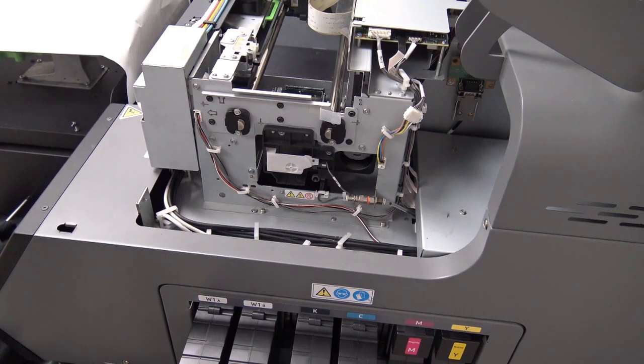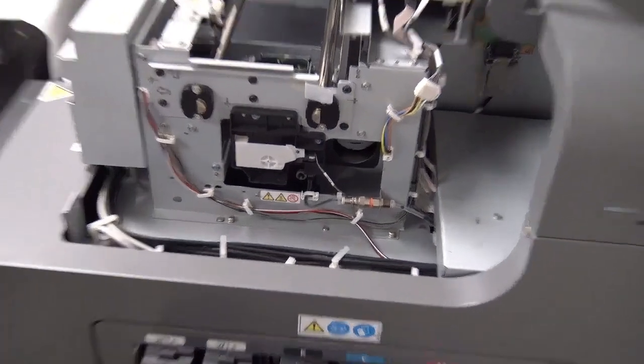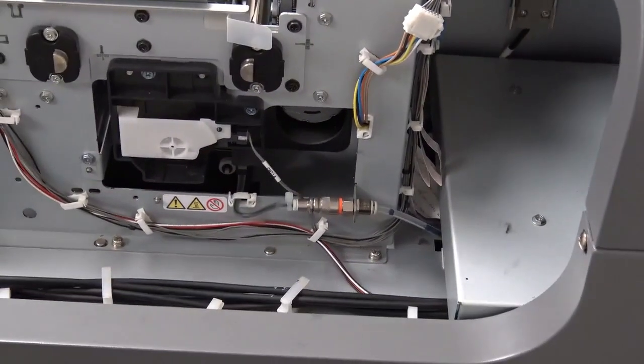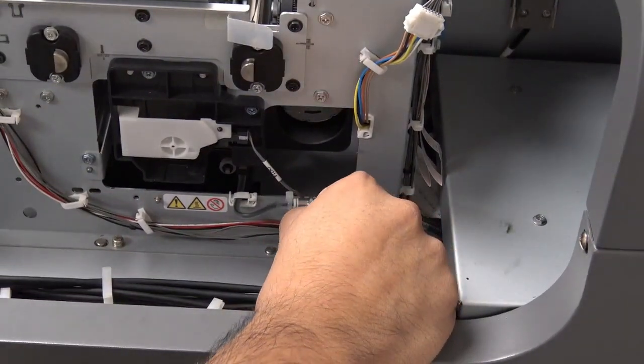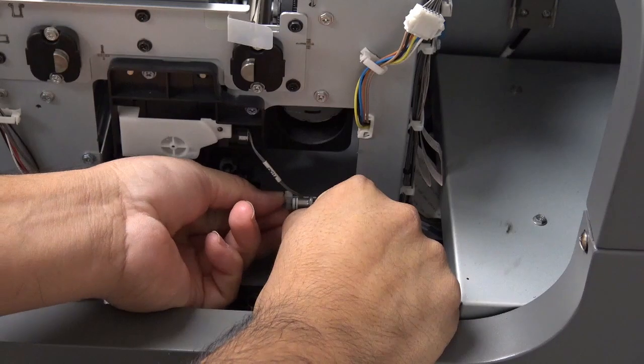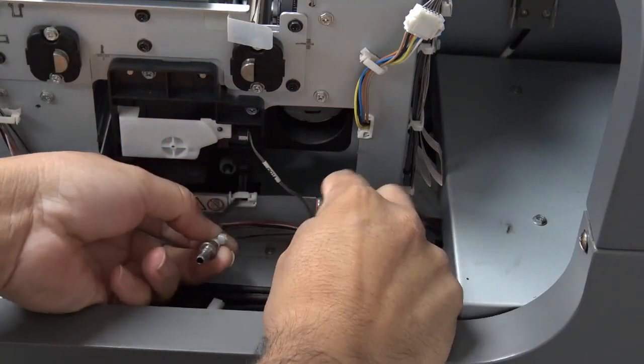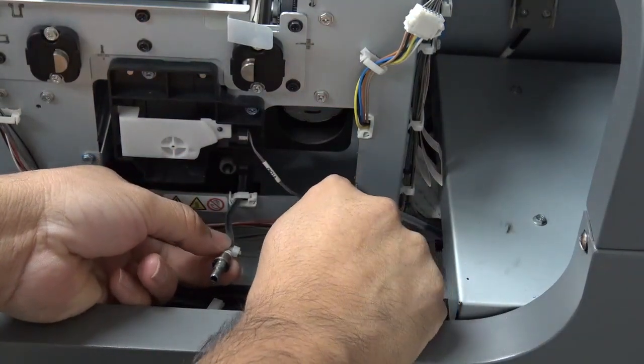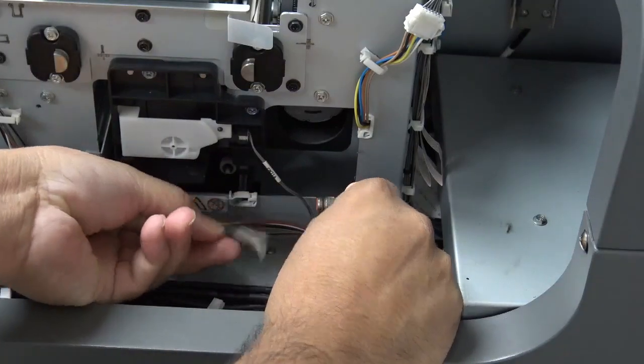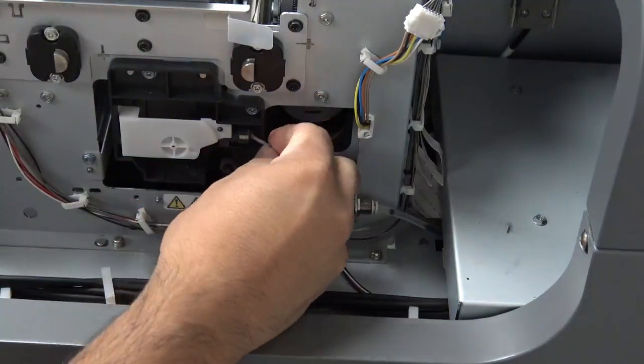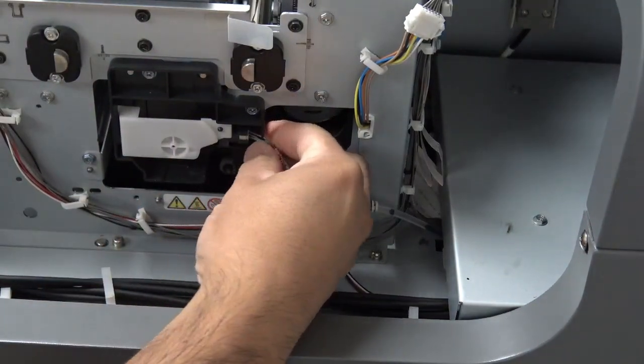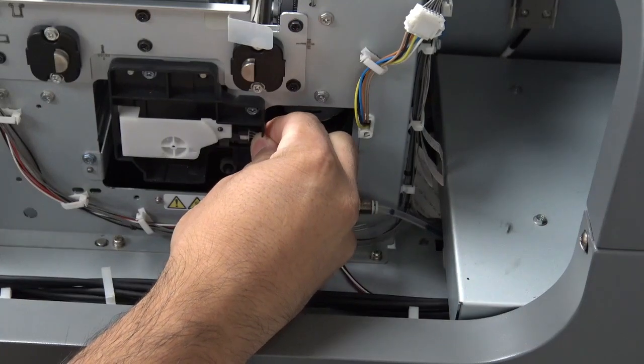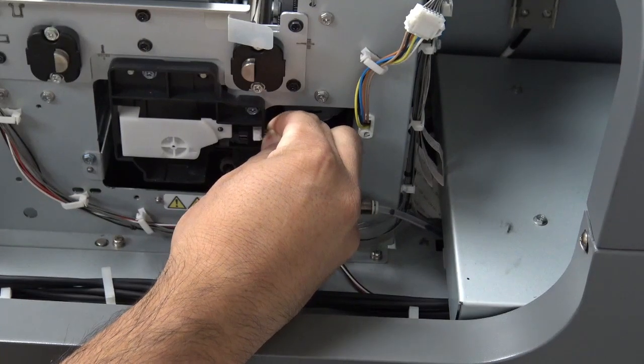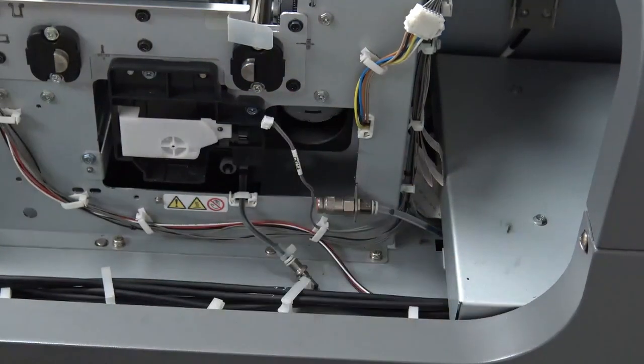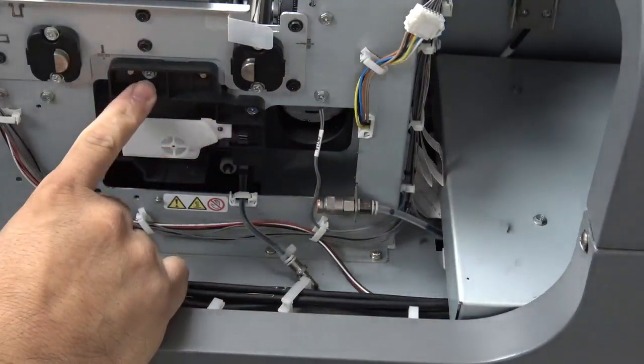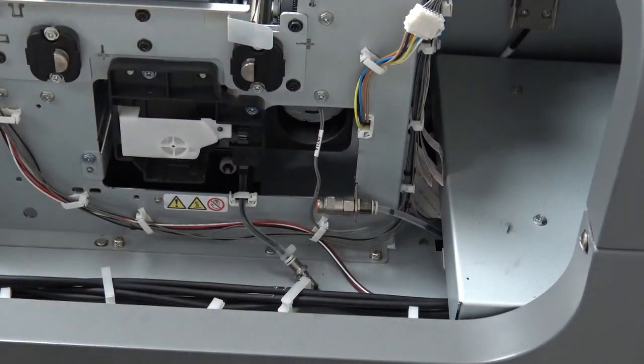First thing we're going to do is we're going to release our waste tube. We're going to push it back on this, and then we're going to pull the tube forward. So this is like a quick release valve, kind of like you see in an air compressor. You push back, and then you pull the tube forward. Next, we're going to remove our power cable here for that sensor. You're going to grab those cables nice and tight, and you're going to pull towards the back of the machine. That disconnects. We're going to have two screws, one here and one right up here. Going to go ahead and remove those screws.